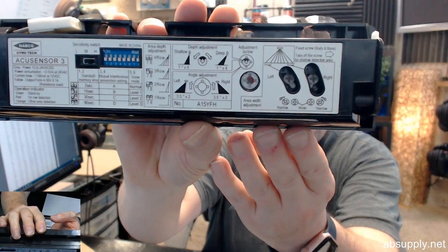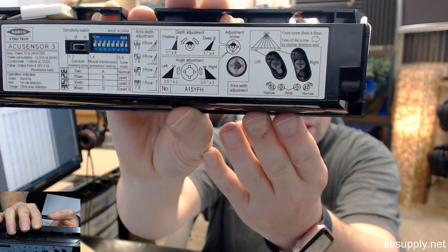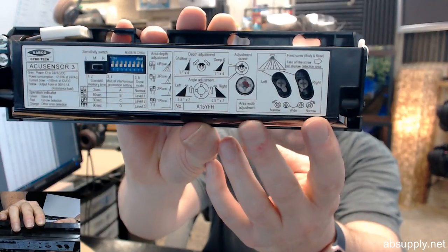Now, setting up for wide coverage is talked about on page 9, and that will allow you to very finely define the actual pattern. So when you look at page 9, you're going to notice that there are beams or rays that are defined in numbers 1 through 8, and it is using the adjustment screw that we're going to see over in this area with adjustment, to tailor exactly what your coverage is going to be, because you might have a certain job site condition that you might need to work around, and being able to define that area of coverage is what you'll do on page 9. Operation setup mode on page 10. Sensors placed close to each other should be on different modes.